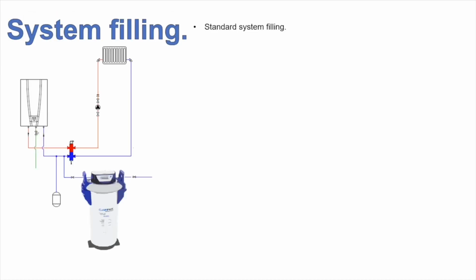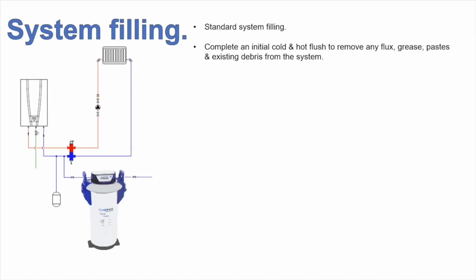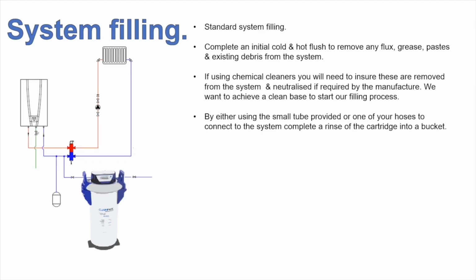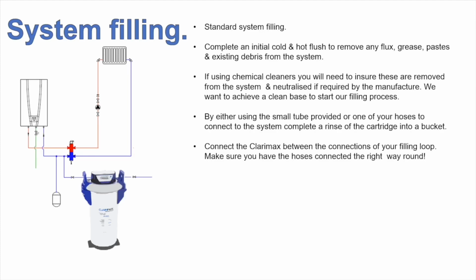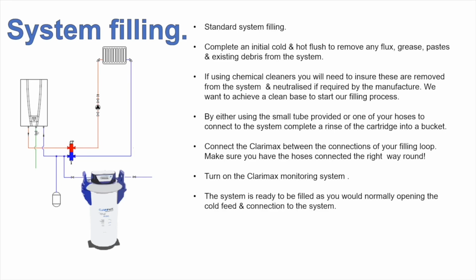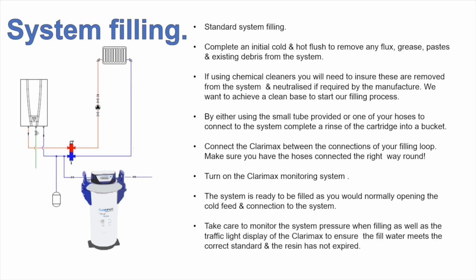A few brief slides here on system filling. We've done a system fill with Alan here today. We need to complete a hot and cold flush. We need to make sure we've removed any flux, grease, existing paste, any chemical cleaners, making sure we get all of them out beforehand. We need to test it. We need to make sure that the water is of the same quality as the incoming main.